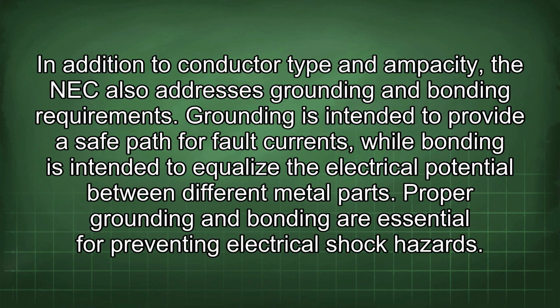In addition to conductor type and ampacity, the NEC also addresses grounding and bonding requirements. Grounding is intended to provide a safe path for fault currents, while bonding is intended to equalize the electrical potential between different metal parts. Proper grounding and bonding are essential for preventing electrical shock hazards.